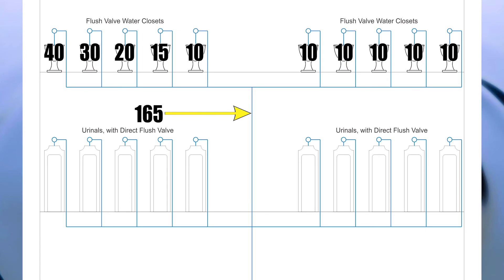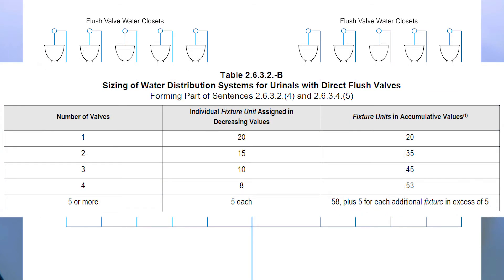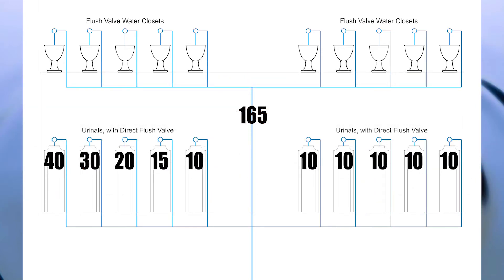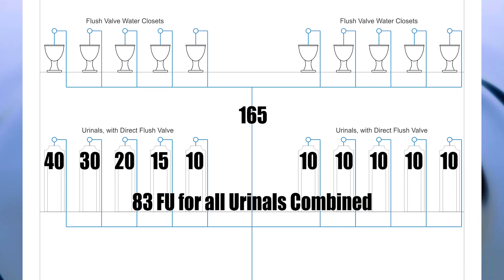We also have urinals on the next story with direct flush valves, so we're going to reference table 2632B and fill in the fixture unit values to calculate the hydraulic load on this pipe. If we add up all the fixture unit values for the urinals we get 83. But for this pipe we also need to add on the 165 fixture units from the water closets, giving us a total of 248 fixture units to size this pipe.